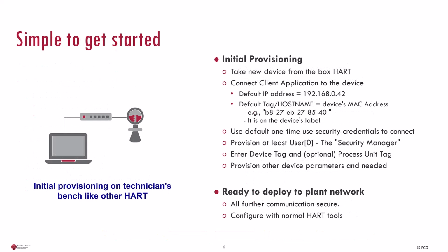We designed HART-IP to be simple to get started with a new device. The initial provisioning wanted to follow the same paradigms you see with HART devices or with wireless HART devices. Take it out of the box, connect it to a client application. For that purpose, new devices have default IP addresses and host names, so you don't have to do anything special to get started. There's also default one-time security credentials you use for this initial connection, and you have to provision at least one set of user credentials, the ones that we call the security manager.